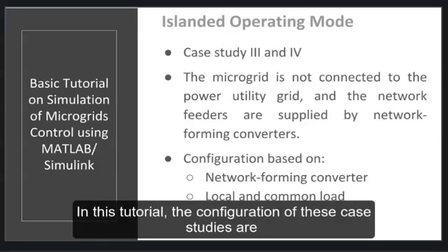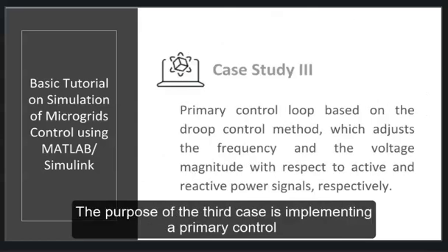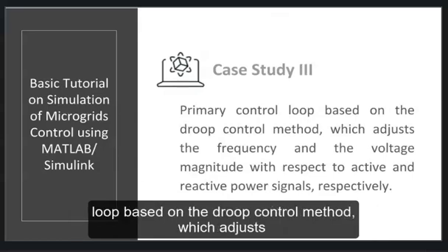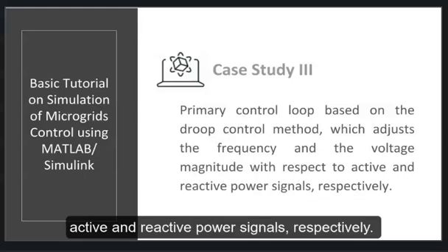In this tutorial, the configuration of these case studies is based on a network forming converter with local and common loads. The purpose of the third case is implementing a primary control loop based on the droop control method, which adjusts the frequency and the voltage values with respect to the active and reactive power signals respectively.